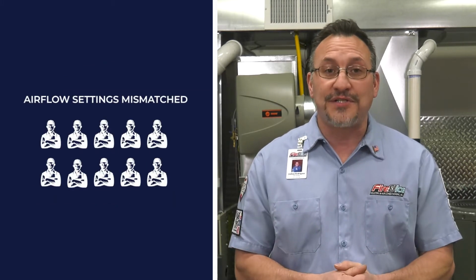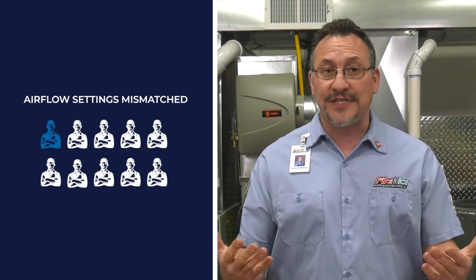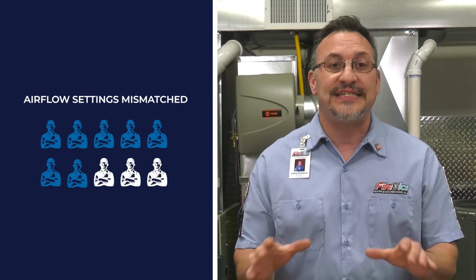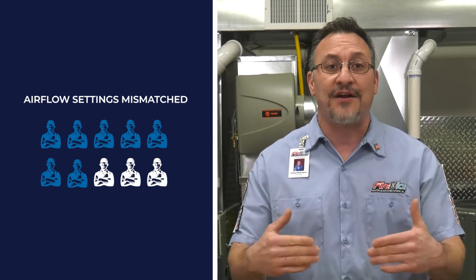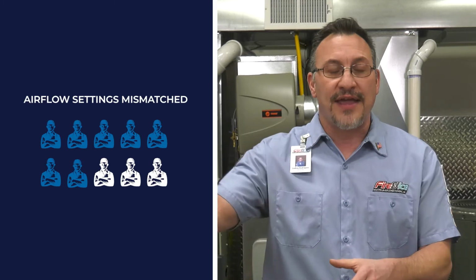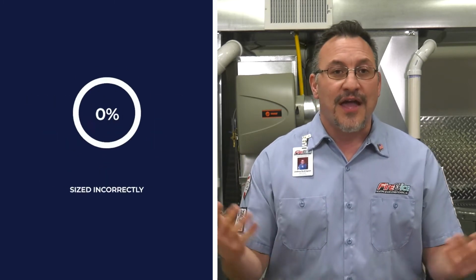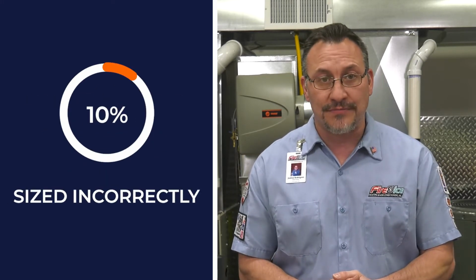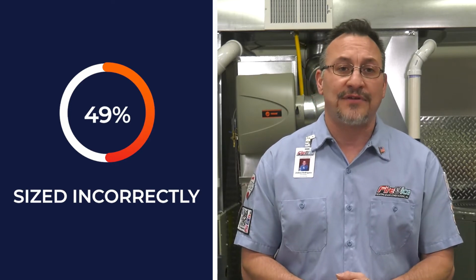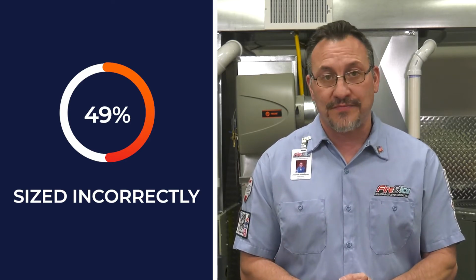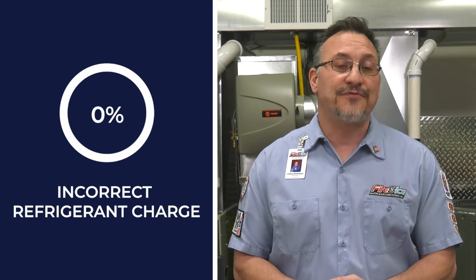A couple other deficiencies found were airflow settings: 7 out of 10 contractors did not set the furnace up properly for the airflow required, given the size of their air conditioner. There was also sizing of the equipment, 49%, almost half, sized incorrectly. There was also incorrect refrigerant charge.